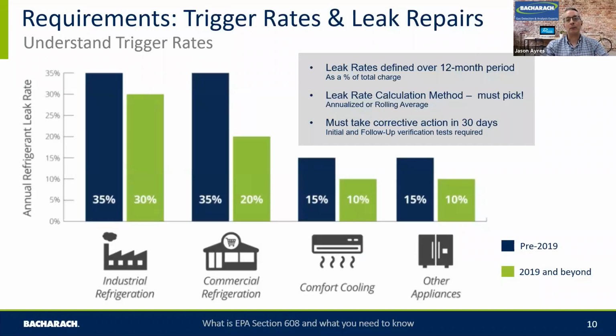The EPA is all about, and 608 is about leak repairs and leak reduction. And you'll hear this word leak rates. Let's define what that means. A leak rate is a percentage of the total amount of refrigerant that's leaked out in 12 months, or leaked out or added back into the system.